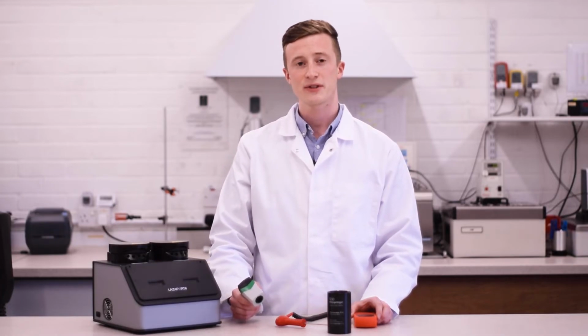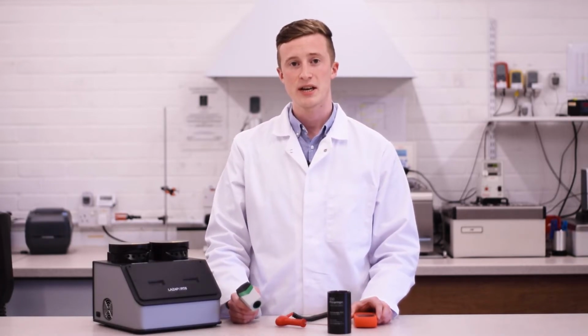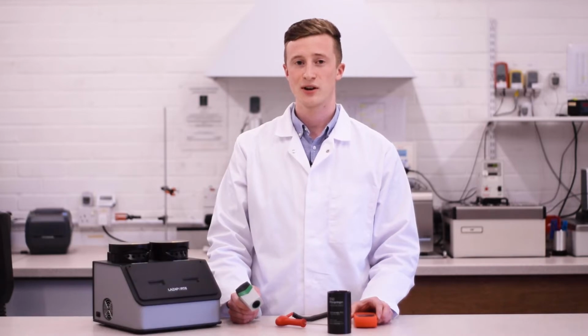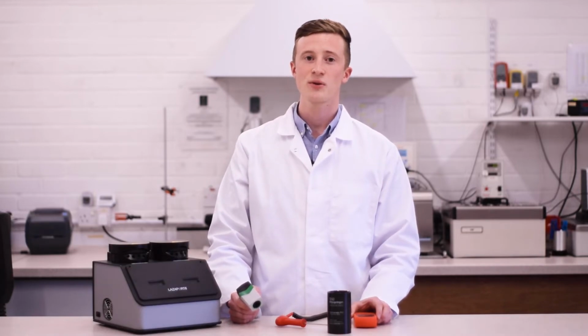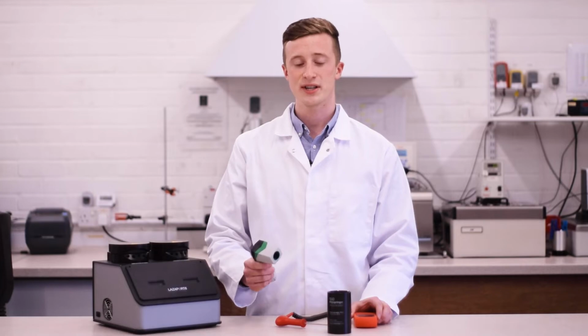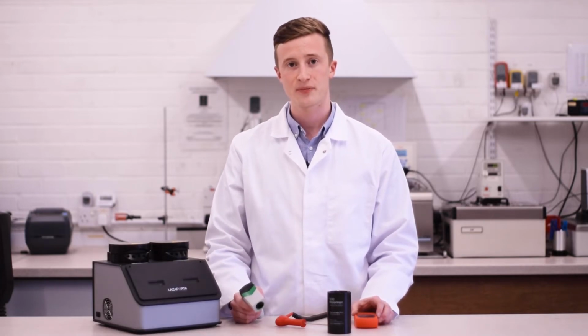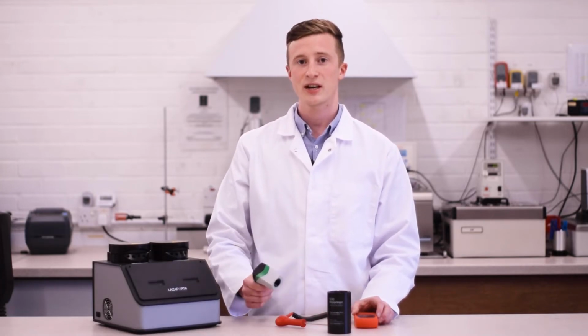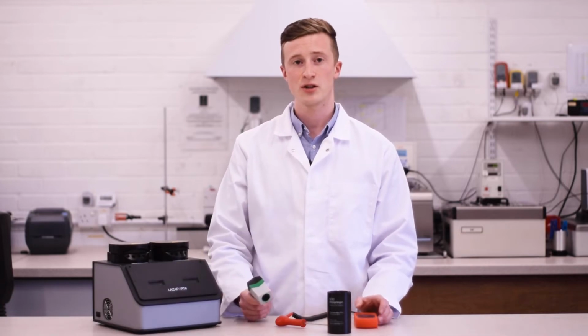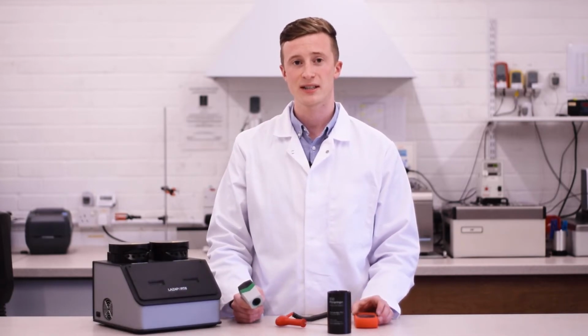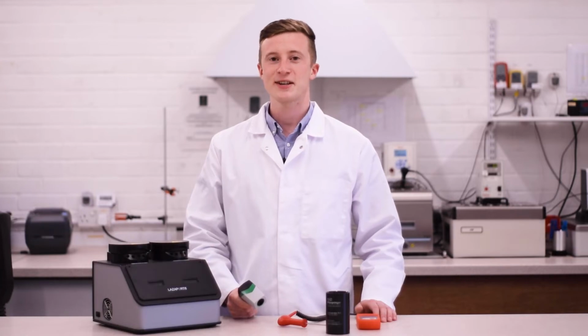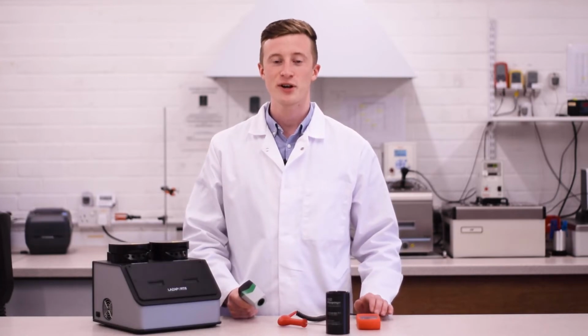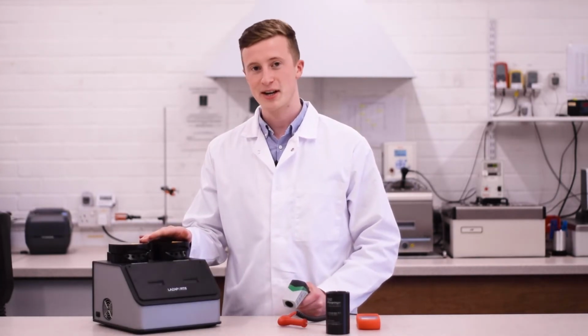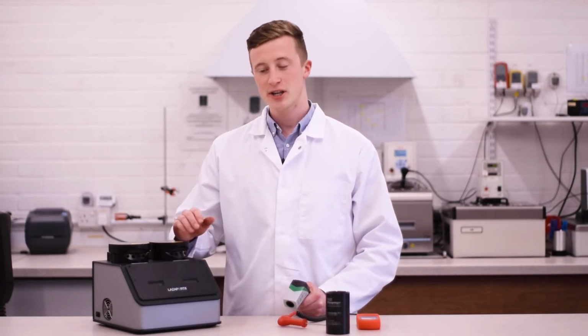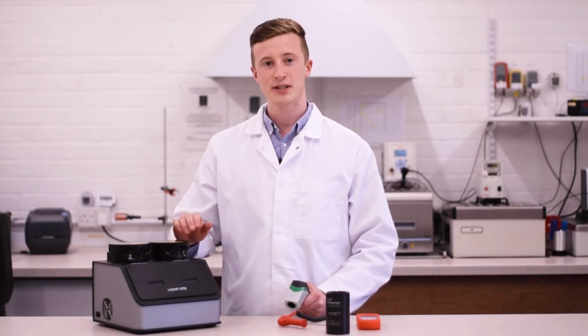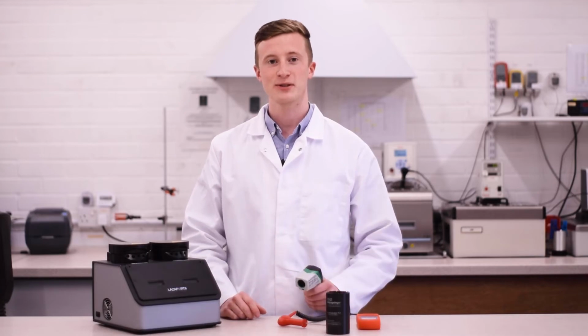If, however, you have several infrared thermometers on site, this process will likely take you a long time. It also only allows verification at one temperature point, which is your room temperature. This doesn't allow you to check the accuracy over the whole temperature range that you may in fact be testing your products at. Because of this, many technical and quality managers now prefer to use the LaserPort 8, which I have here. This has 2 temperature blocks at the top of the unit, specifically for checking infrared thermometers.